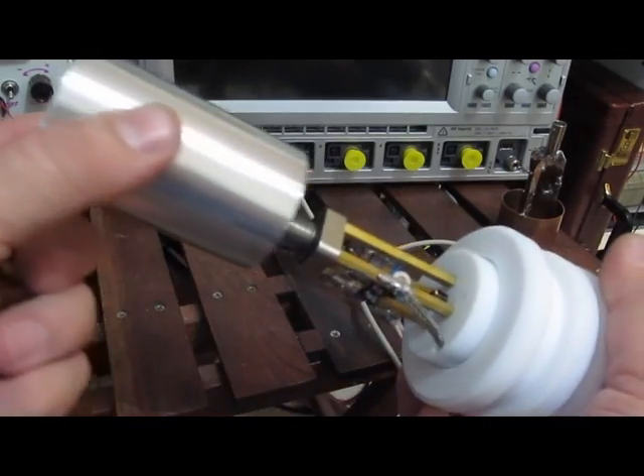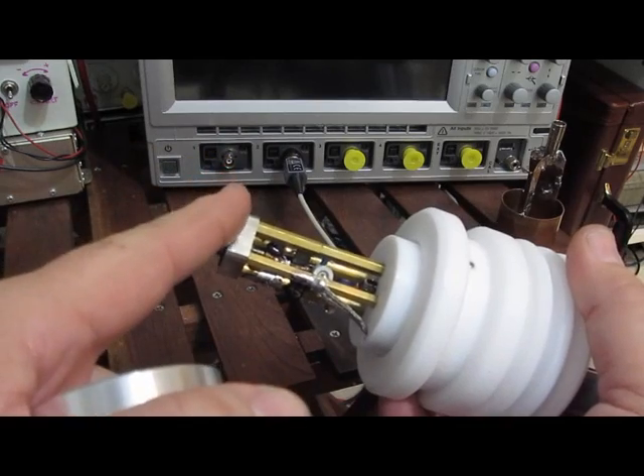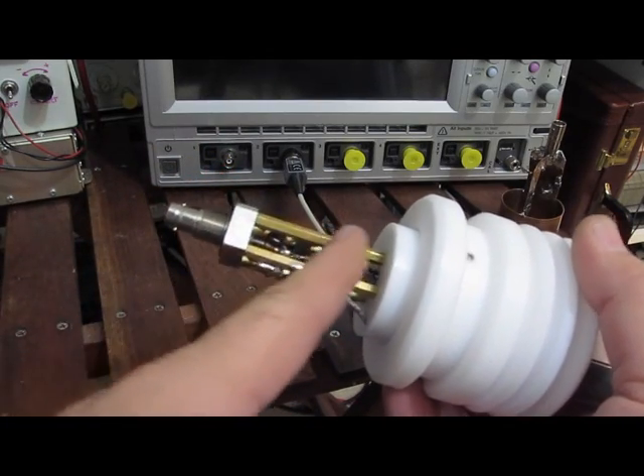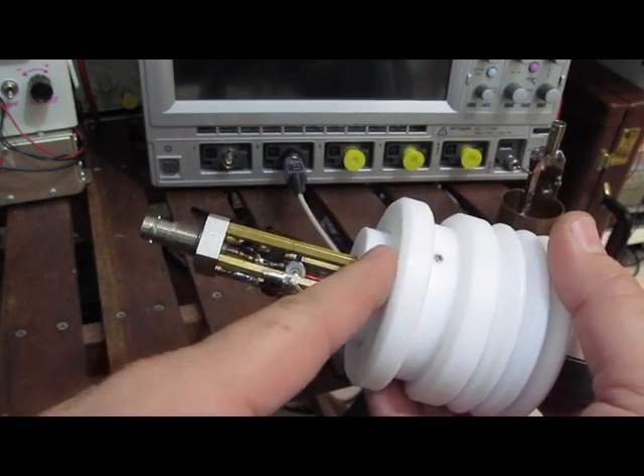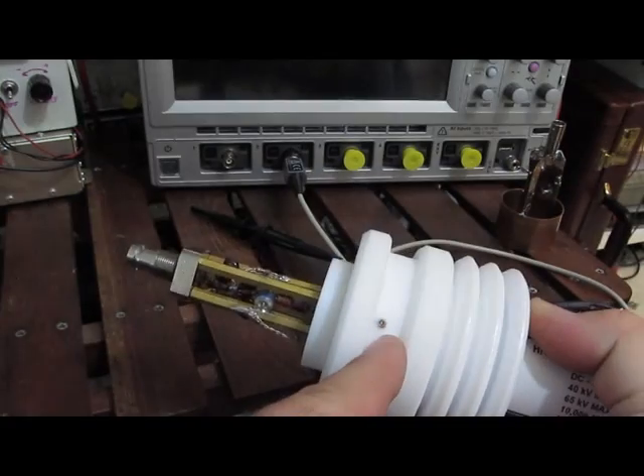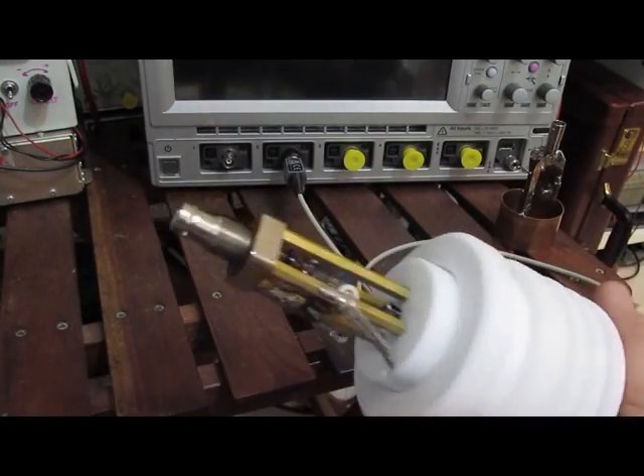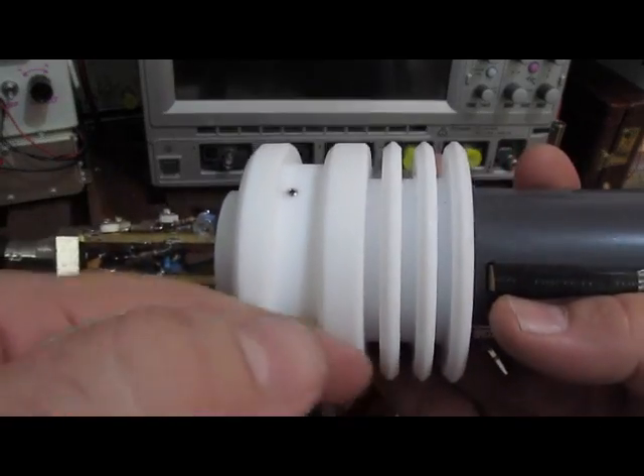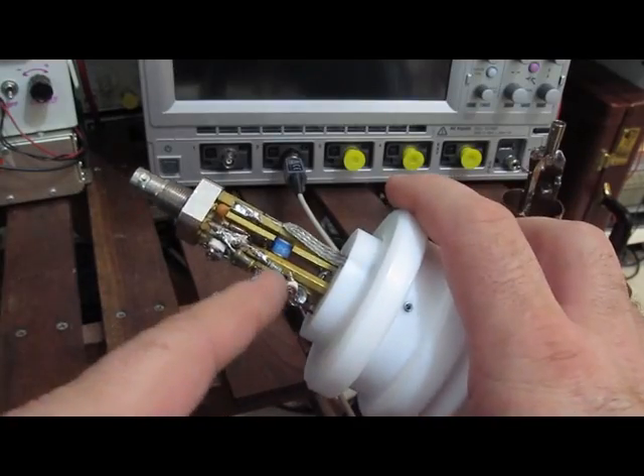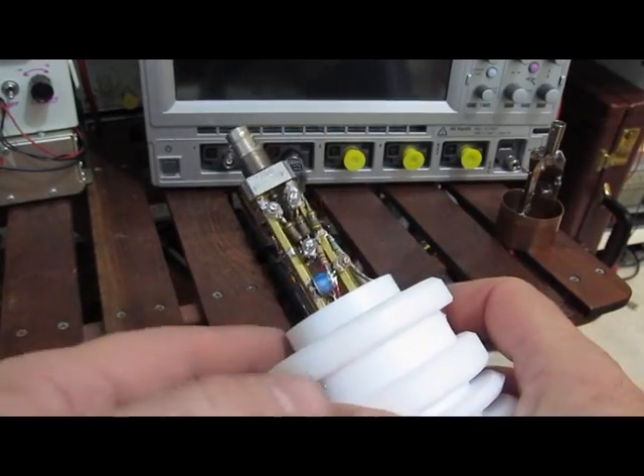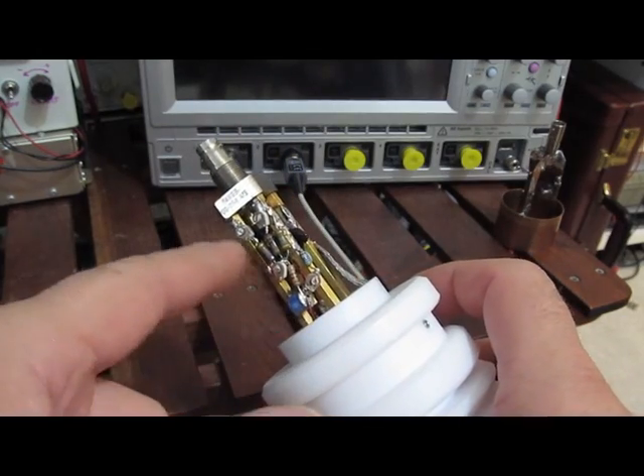That comes off here. The BNC is held in place with these 4 standoffs, and then they're mounted to a Teflon spacer, which is then held in place with 3 set screws located along the main insulator. You can see I've removed the MOVs, but I've left the 2 GDTs and the transorbs in here. These are the 4 calibration adjustments in it.